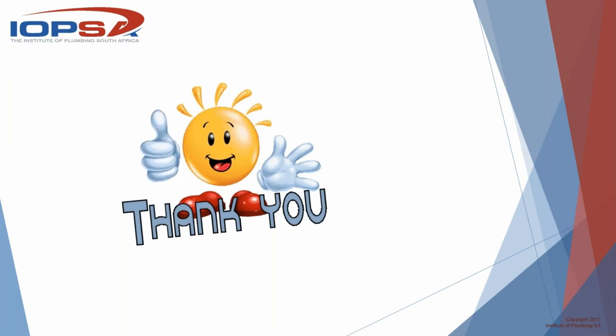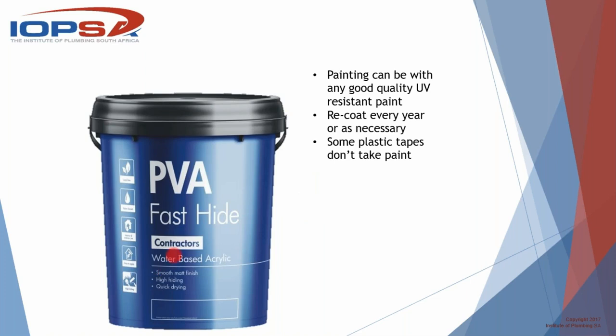Okay, so once again, we go back to the painting. I use 100% acrylic PVA paint. I can even tell you the manufacturer, but it wouldn't make a difference because there are many manufacturers. But if you just paint it properly, it's a multi-tiered process. You need to start off with good, well-installed lagging. So it needs to be R1. It needs to be mitered at the corners so that the joints between the lagging come together and you can glue them together so that there's no physical gaps. If necessary, put some tape around them.